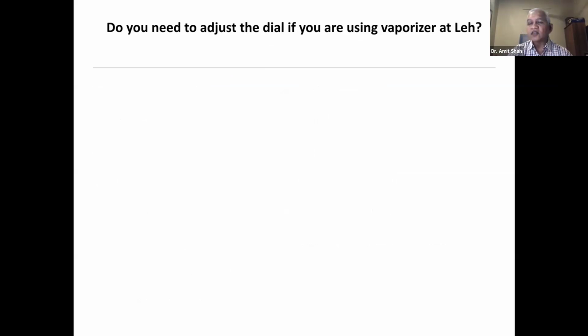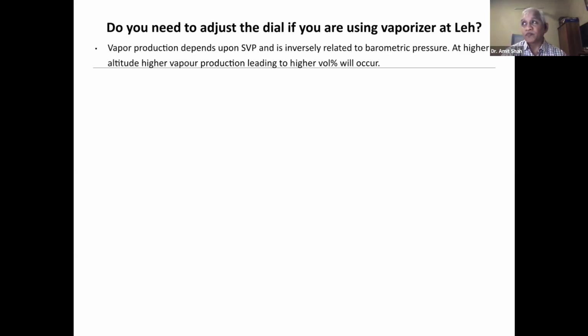Now, one important understanding. We know that when you go to a higher altitude, the flow which passes through your anesthesia machine can change. The pressure drops and it depends upon the viscosity, and that is why the flow would be higher than usual. Does it happen with the vaporizer output? Now vapor production depends upon saturated vapor pressure, and it is inversely related to barometric pressure, because it is at a specific temperature, and the atmospheric pressure would be lesser, right?